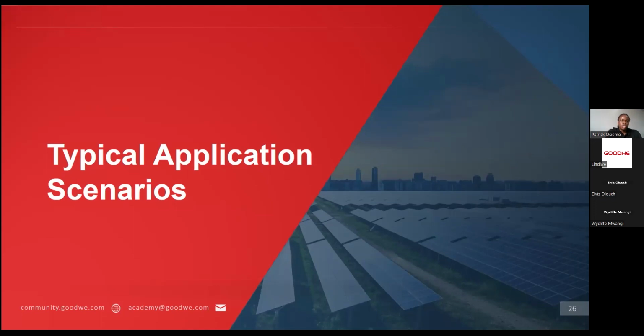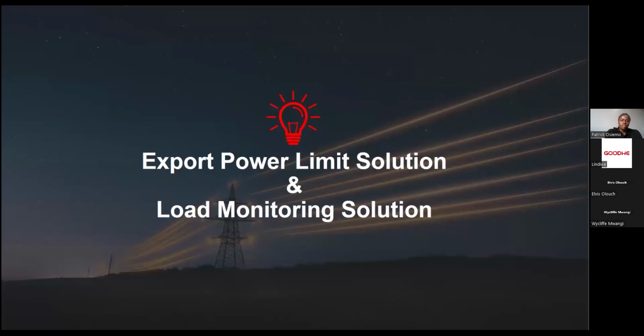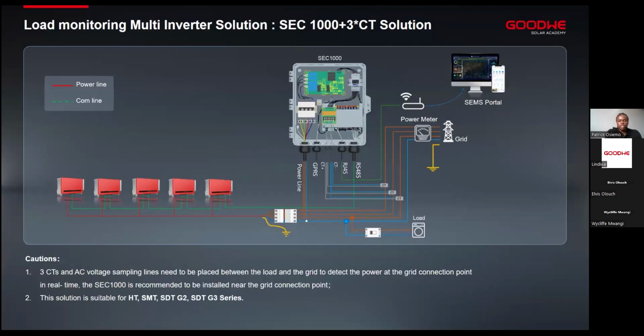I do have a number of typical application scenarios that our products are able to be utilized in. For example, in case you want to do export power limits or load monitoring, GoodWe does offer this kind of solution. How do we get to utilize this? For example, you can do load monitoring and zero export through the SEC 1000. SEC 1000 is a very robust controller, with up to 3 communication ports for your PV inverters. Each port can hold a maximum of 20 devices, so you can do up to 60 devices for the SEC 1000. The SEC 1000 has very unique features because you can do dynamic reactive power control.